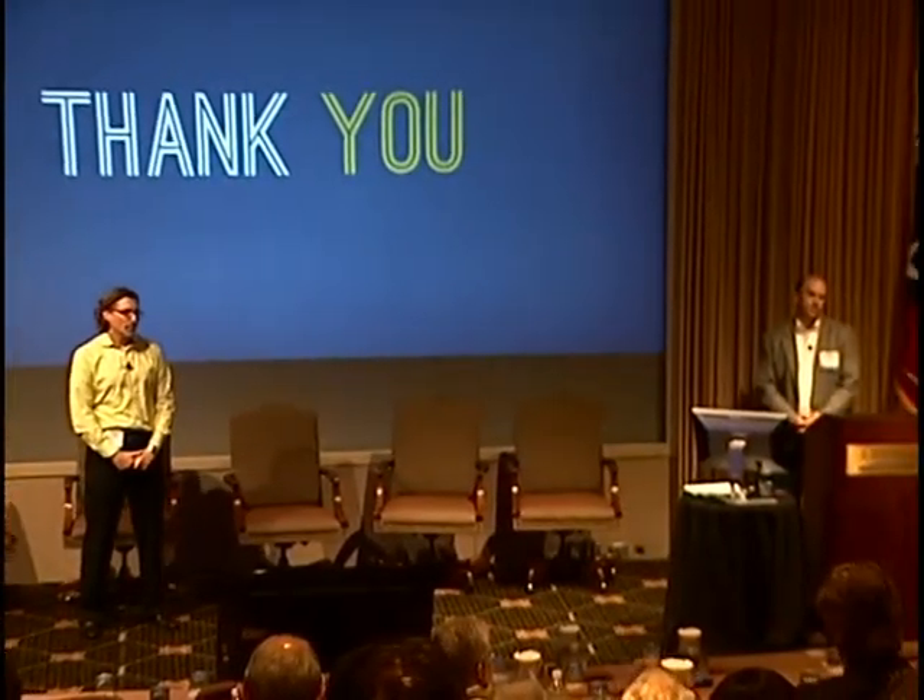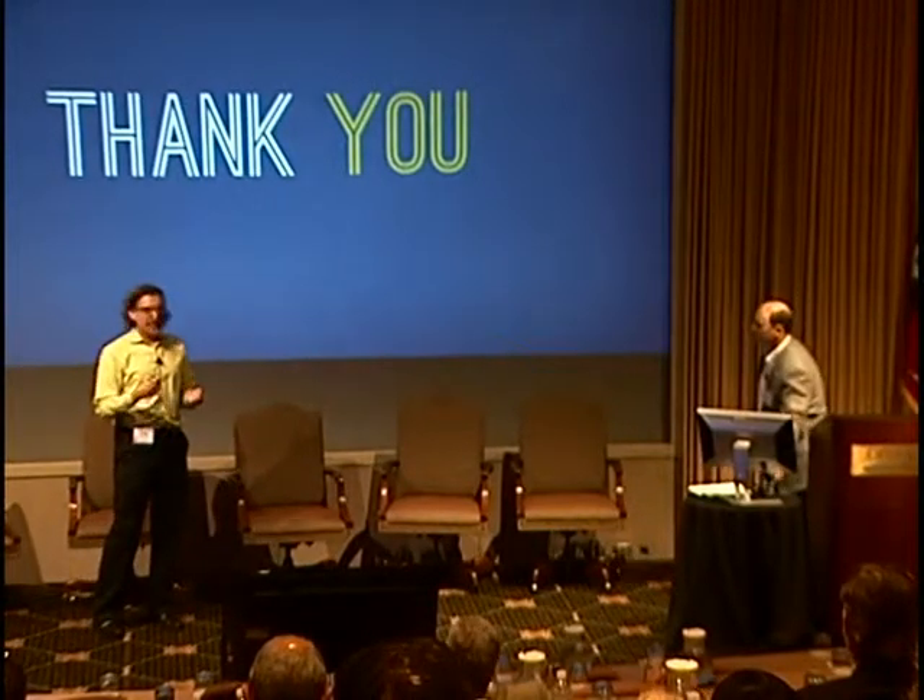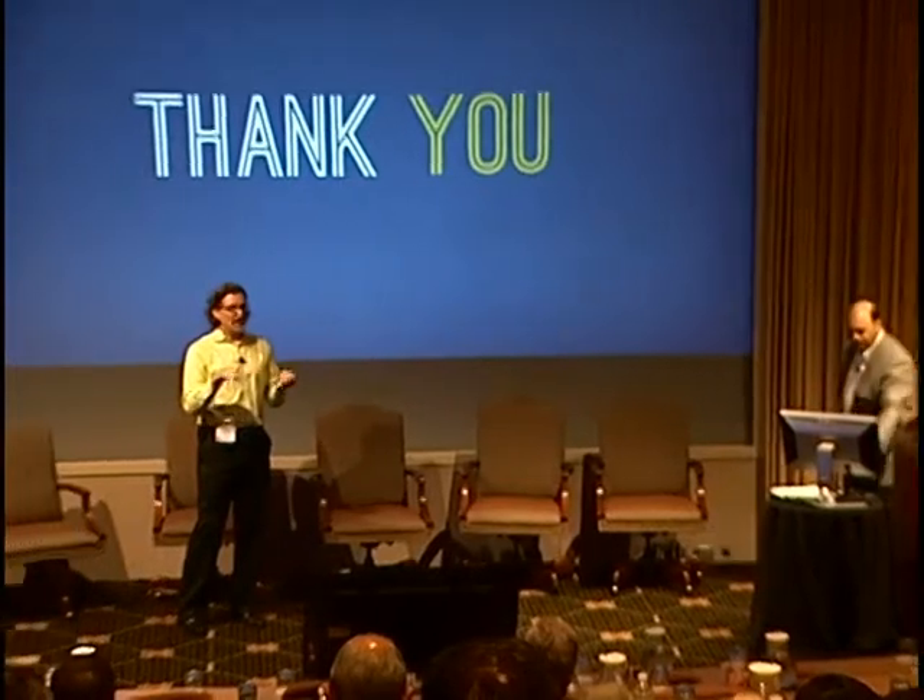On the question of whether a similar productivity curve is seen at the manufacturing level: right now our perspective is it's been cost-neutral, which is where we got started a couple years ago. We've done about seven rooms now — roughly 14 megawatts of utility load. It was really a time savings thing initially, and we're seeing costs come down as we order more. We have probably 12 electrical rooms delivering 1,125 kW to the floor on order right now for various projects. It's a huge capital commitment, and you start to see savings as quantities go up — absolutely, because you're paralleling activities.